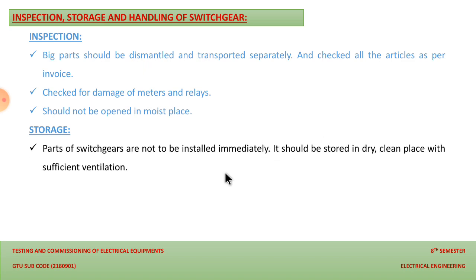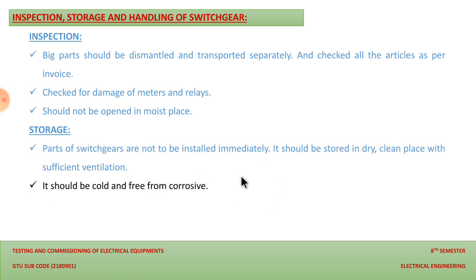Then the storage. Parts of the switchgear are not to be installed immediately. It is necessary that first of all we check for all damages, and perform certain tests related to the switchgear. So it should not be installed immediately, and it should be stored in a dry, clean place with sufficient ventilation. This is the most important point while we are putting our device in storage. It should be cool and free from corrosion. The atmosphere must be free from moisture, as we have already discussed, and the place where we are storing this device should be corrosion free, so there will be no chances of accumulation of corrosion inside the switchgear.